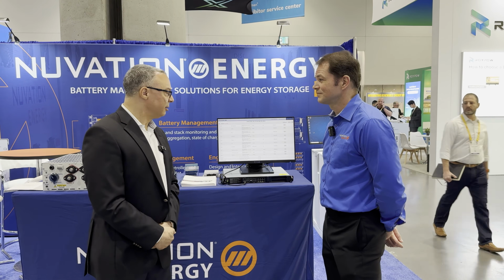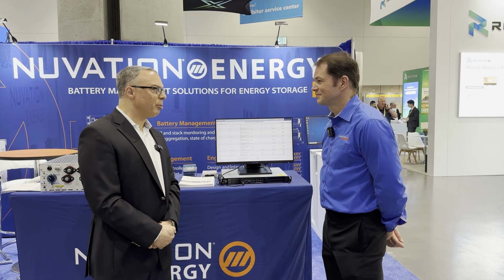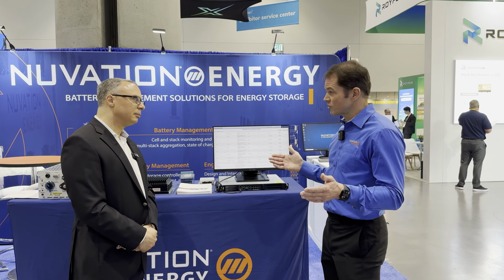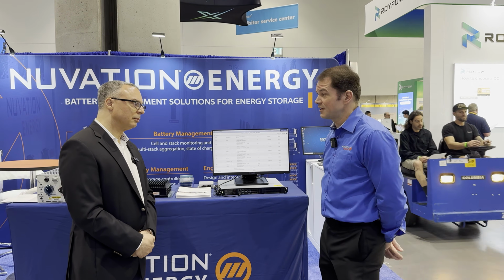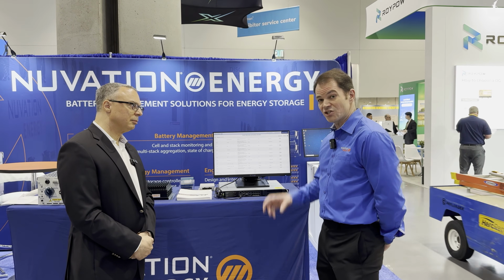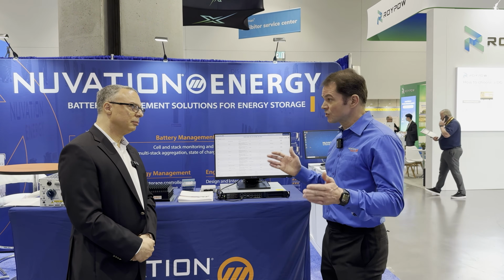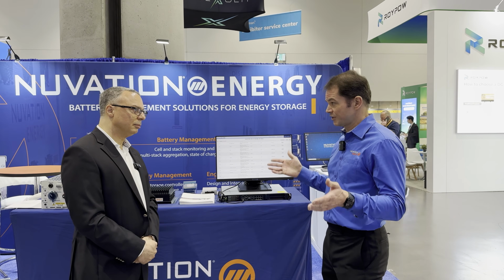That's really impressive, Michael. So how does one provide so much flexibility without compromising battery safety? Great question. The way we do it in the Nuvation BMS is we actually have two sets of registers. One set is locked down inside of the UL 1973 functional safety process — it actually has a CRC check on it. These are the ones that keep the battery fully functionally safe.